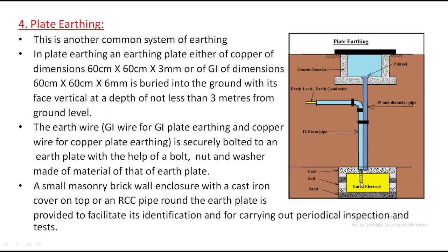Why is it called the earth electrode? From this point to this point, the leakage current enters through this earth electrode only, and through this earth lead. From this point the leakage current or short circuit current enters into this plate, and the plate supplies it to the ground. And this is the funnel. From this point we can pour water to maintain its conductivity, and there we also have sand, salt, coal, all the elements kept here, and it is kept vertically.